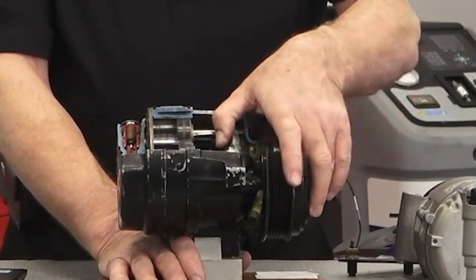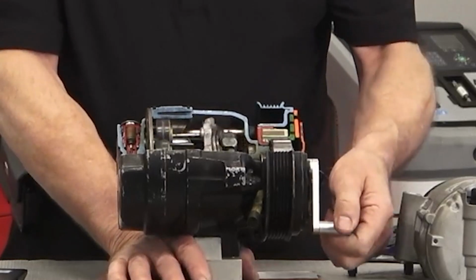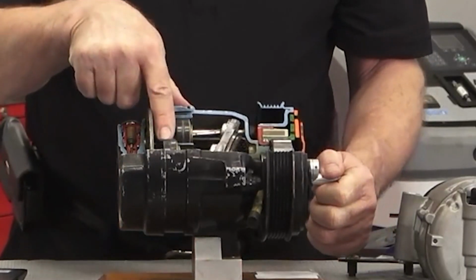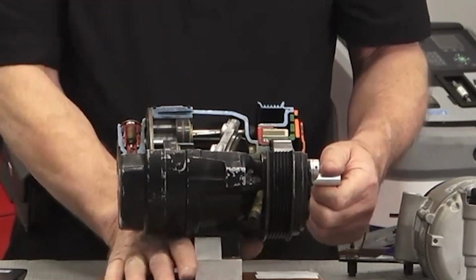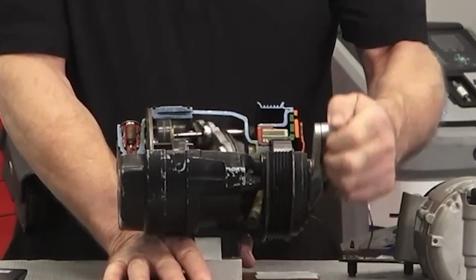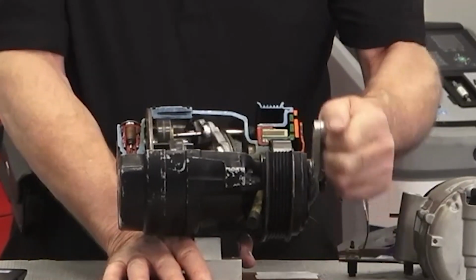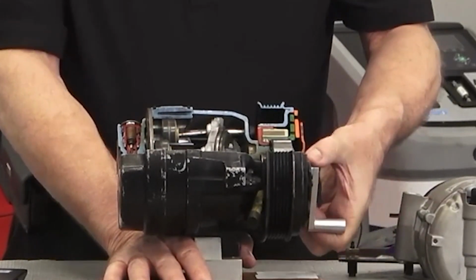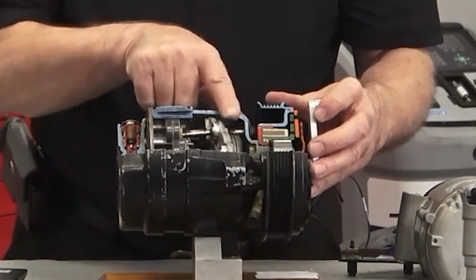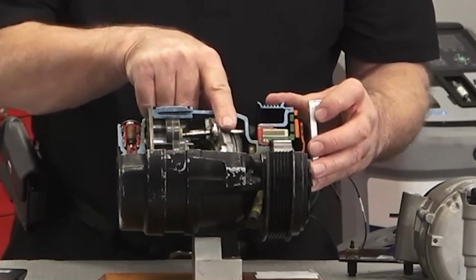As you can see, when I turn this compressor by hand, here are my pistons - this is my piston right here - and you can see that as I turn the compressor by hand, the piston is going back and forth pretty easily. What's unique about this compressor is it's got what we call a wobble plate on this older design. Most modern systems call it a swash plate.